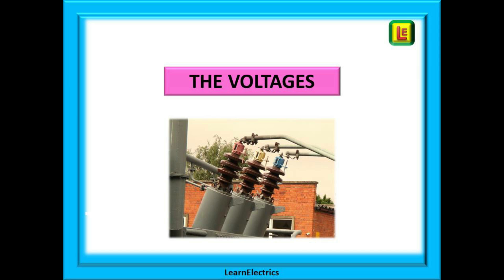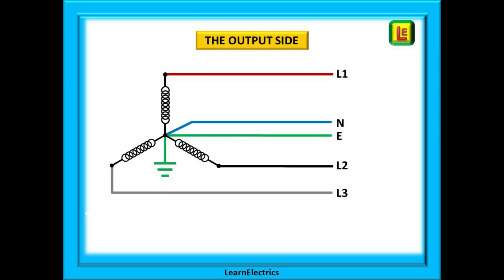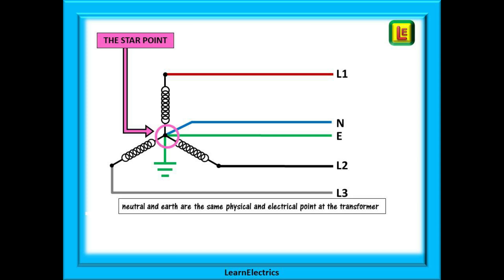We can look now at the voltages on the output side. We will only show the secondary side of the transformer now, the output side, since this is the part that is of most interest to us. These are the cables that go to the houses, the shops and the factories. Notice that all three windings and the neutral and the earth are all connected at the same point. This is called the star point, the common point. And it is here that the neutral and earth are electrically and physically the same point.